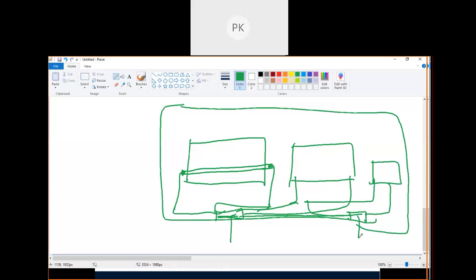So the two connections are for redundancy? Yes, it is for redundancy only - you are correct. Two connections are for redundancy. And when we calculate, if my fault current is 50 kA, each of these has to carry 50 kA. You cannot say this will carry 25, this will carry 25. Each of them has to carry 50 kA.